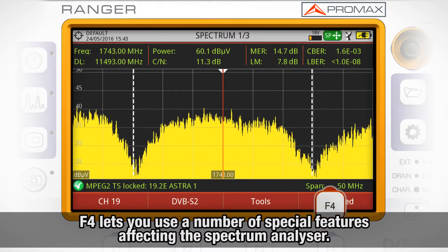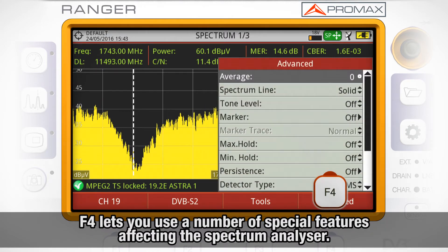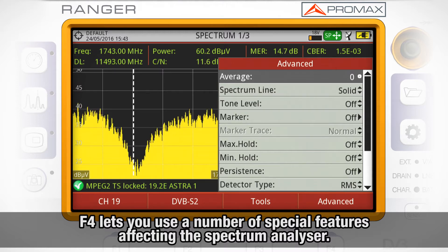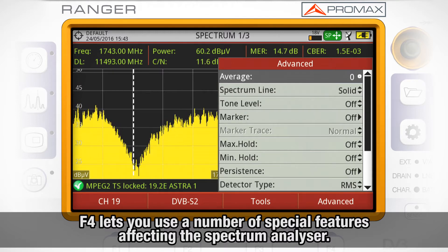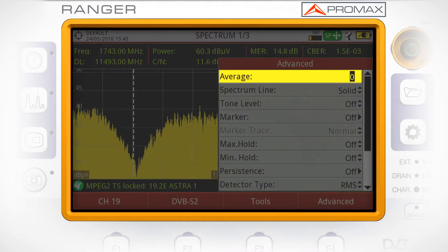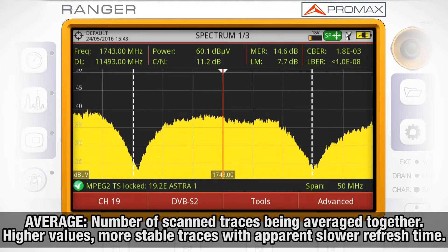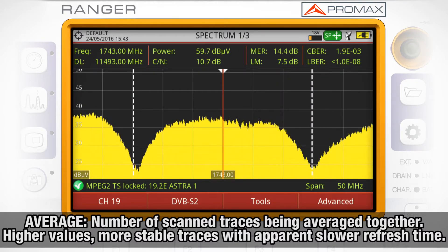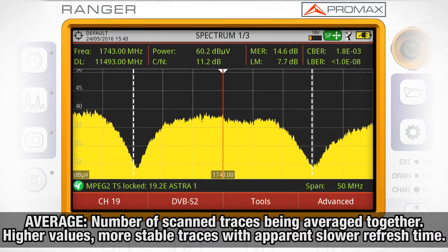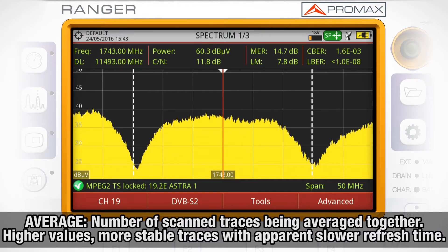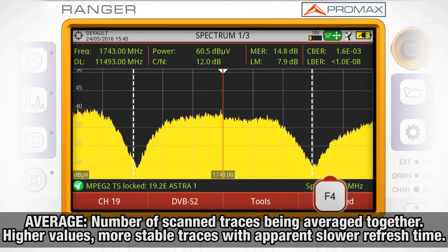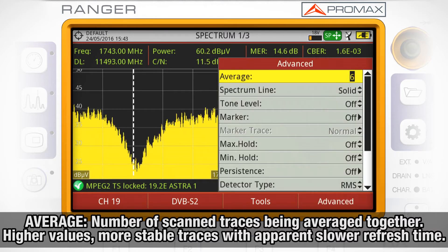Finally, F4 lets you use a number of special features affecting the spectrum analyzer. Average: the higher the value here, the higher the number of scanned traces being averaged together. Therefore, the higher this value, the more stable the trace will be and the slower the spectrum analyzer will appear to be.